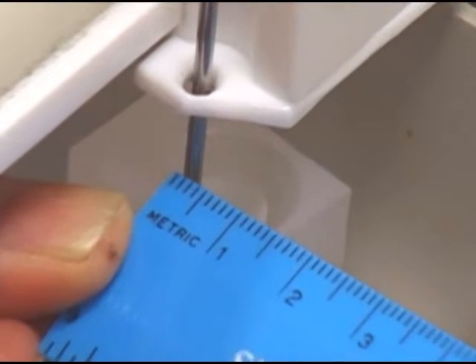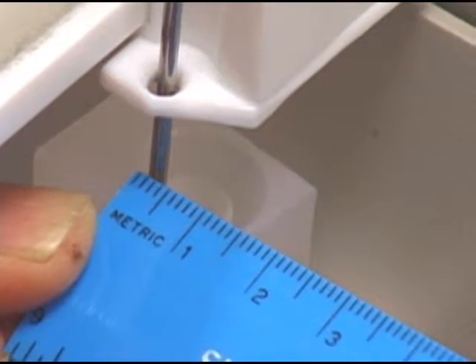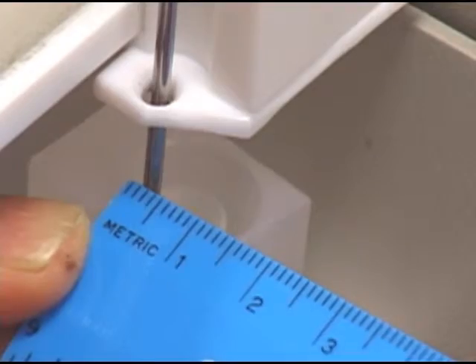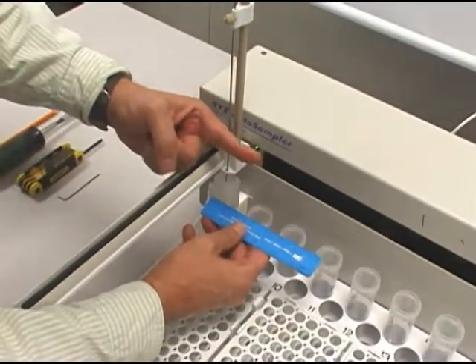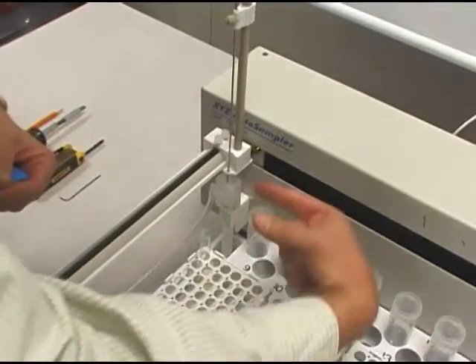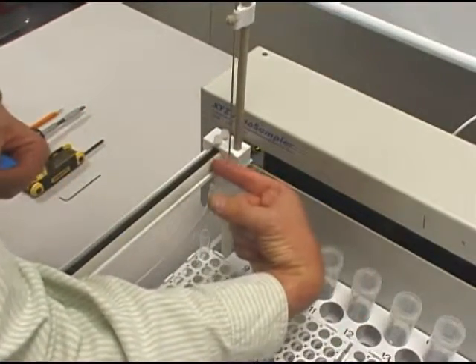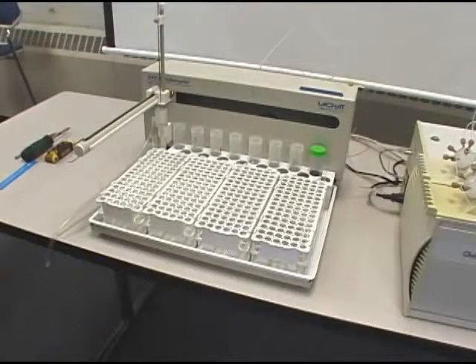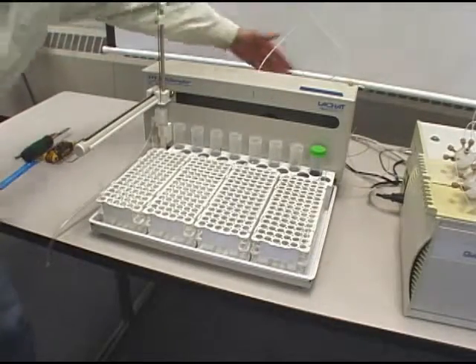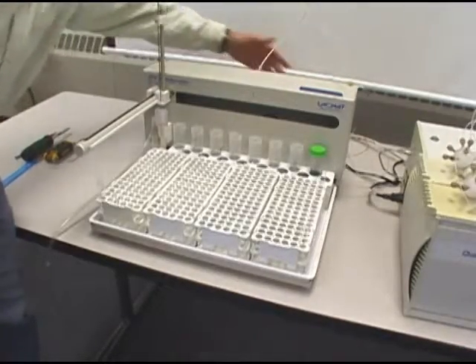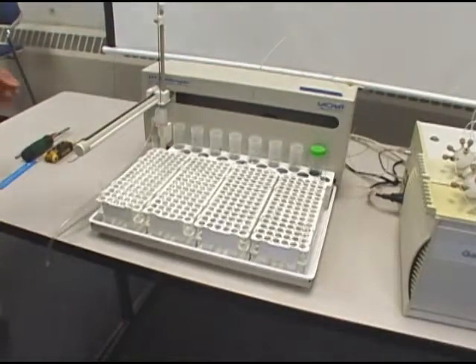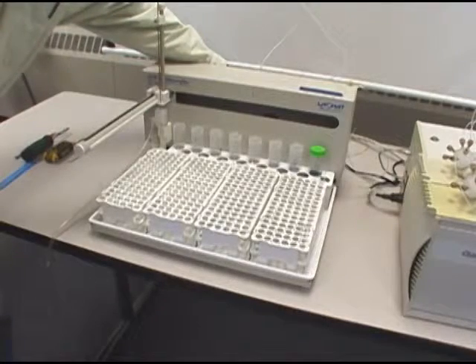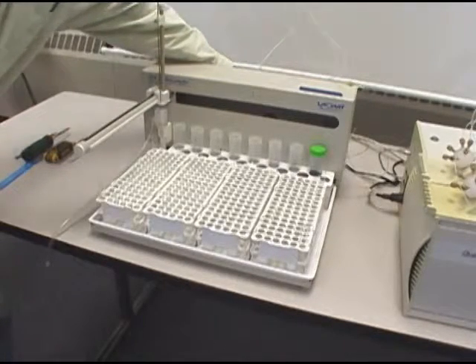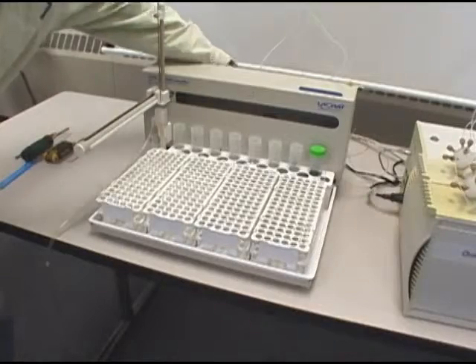So with the ruler, I measure from one side of the probe and notice that I need to move about 4 millimeters in this direction. I need to move the probe in that direction, or alternatively I need to move the wash bath in that direction 4 millimeters. Okay, so now we're going to show you how to adjust the wash bath. First of all, I want to turn off the instrument. And I'll raise the probe a little bit from the linkage in the back. Raise it out of the way.